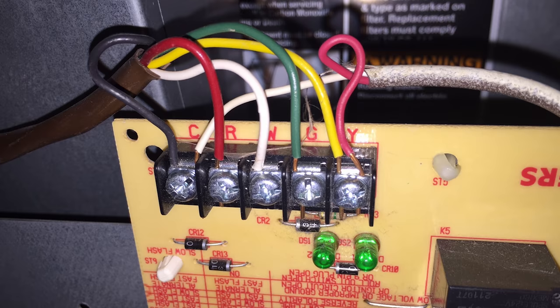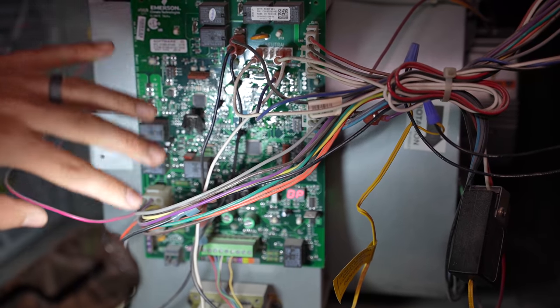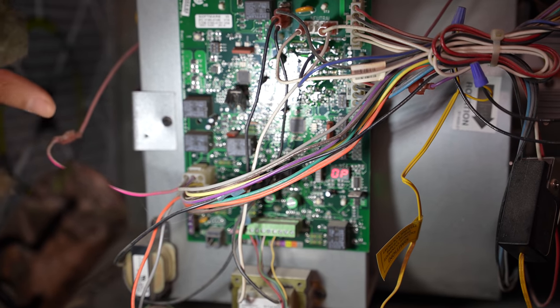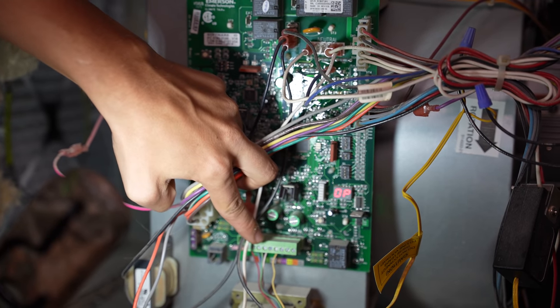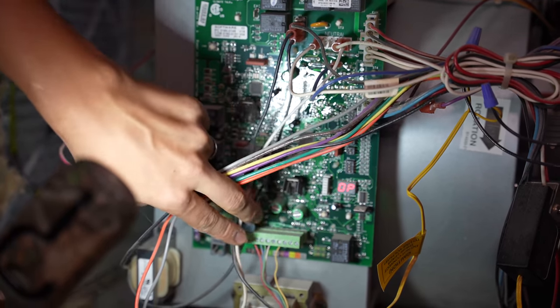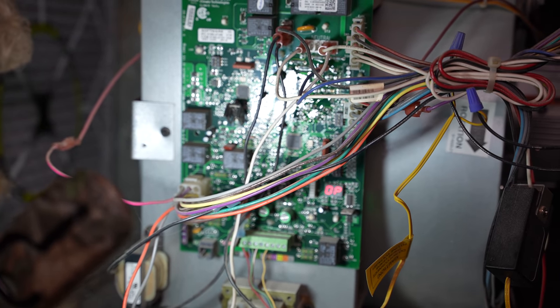Others will look a little bit different, and then there's furnaces that don't even have a control board, and most people that have that question, usually that is the case. They don't have a control board, they don't have this 24 volt terminal strip, and that is why they're struggling to find their 24 volt common.